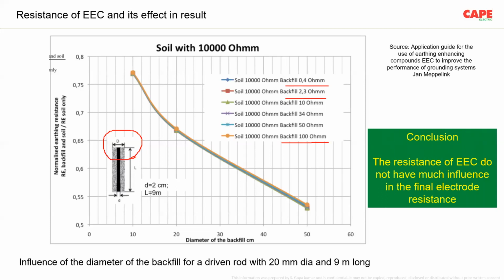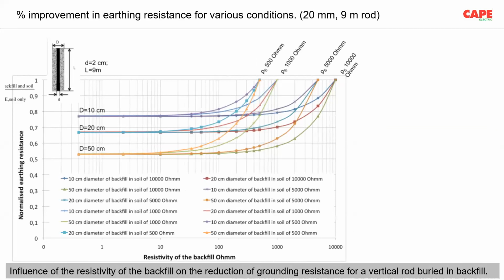Why I put this into the presentation is, a lot of times customers call us, saying I need an earth enhancing compound of 0.12 ohm meter. Somebody asks, I want an earth enhancing compound of 0.2 ohm meter. Actually, whether the resistivity of the earth enhancing compound is 1.2 ohm meter or 0.12 ohm meter or 12 ohm meter, it actually doesn't matter. You can see here in the table, with a backfill compound from 0.4 ohm meter to 100 ohm meter, the final result is almost the same. There is no big change. The conclusion is the resistivity of the earth enhancing compound actually doesn't matter.